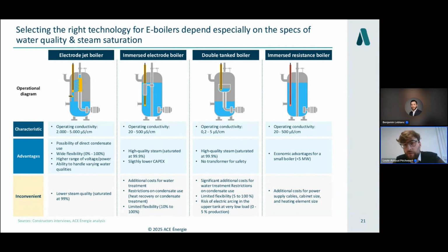The real difference between electrode boiler and resistance boiler is the power available. Above 5 megawatts, you will work on electrode boilers, and below 5 megawatts, you will work on resistance boilers. Between 1 and 5 megawatts, you can investigate both electrode and immersed resistance boilers. But if you are above 5 megawatts, resistance is just not cost effective at all.